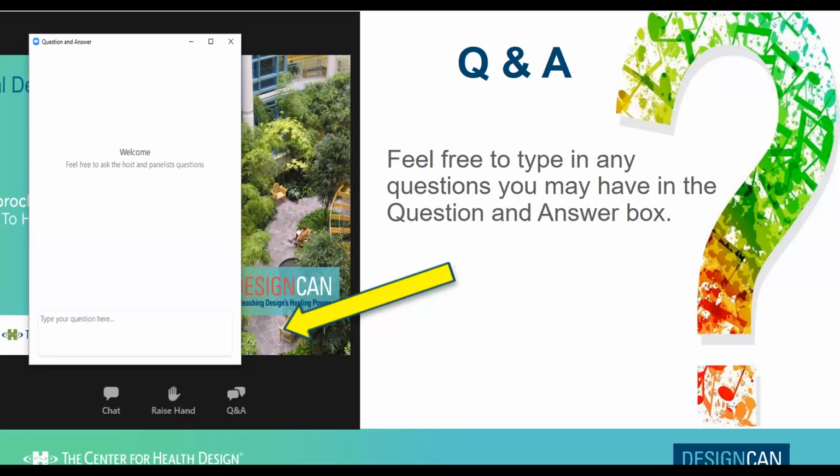Wow, okay, great. So Frank sent us a great question, so I'm going to try and get through it. One of the traditional arguments for unidirectional airflow over the surgical site in the OR is the ability to maintain minimal airborne infection risk over the site. Does this agree with your research? And are there implications to the ICU airflow? Yes, that does agree, and that is what we find, is that the more efficient and effective unidirectional downward airflow over the sterile field or the patient bed does very definitely reduce the risk of microbial contamination in that space.